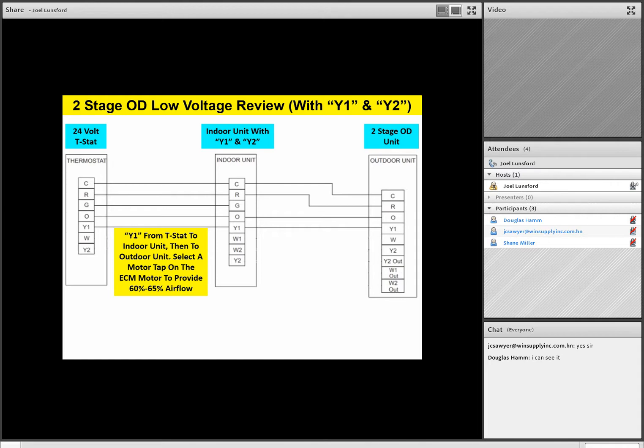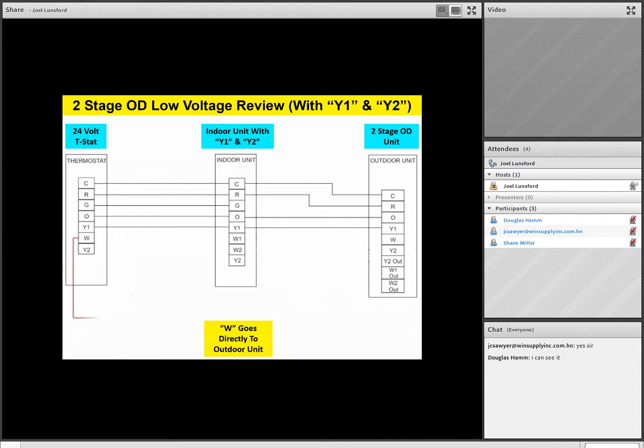Then we're going to take W from the thermostat, and we're going to take it straight outside. We're not even going to touch W1 or W2 on the indoor unit, because what we're going to do with our two-stage heat pumps like that, we have the capability of actually letting the outdoor unit stage the heating based on outdoor temperature. Now, if a contractor doesn't want to do that, they can let the thermostat do their staging if they want to, and not even use that W circuit outside. But the most common way we see this being hooked up is you have W from the thermostat straight outside, and then we're going to allow the outdoor unit to stage first and second stage auxiliary heat.